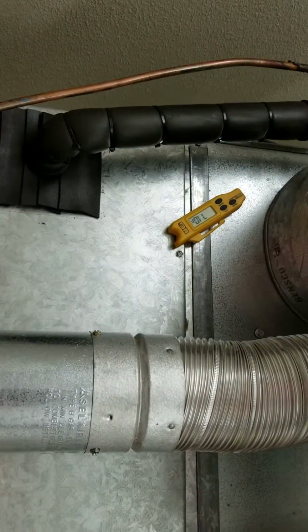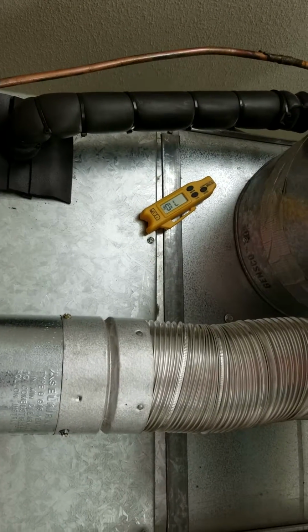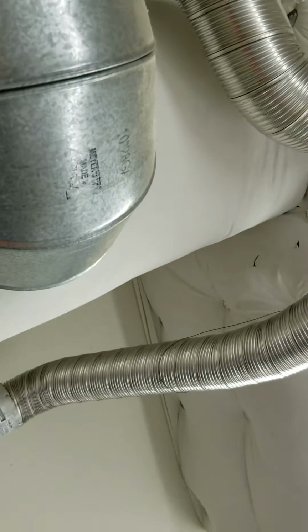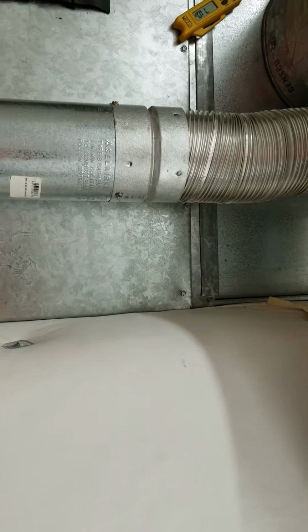And then the other thing, of course, your supply air temperature up here, the thermometer that we've installed. The other thing you're going to want to do is inspect your flue. Make sure your flue pipe is not broken or has no holes or anything in it, to make sure that it is indeed safe for our homeowner. That's why we're here, is to keep our homeowner safe as much as possible.